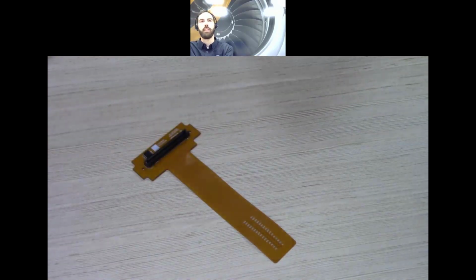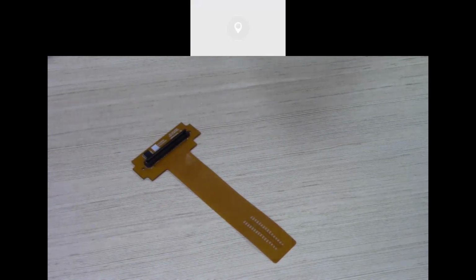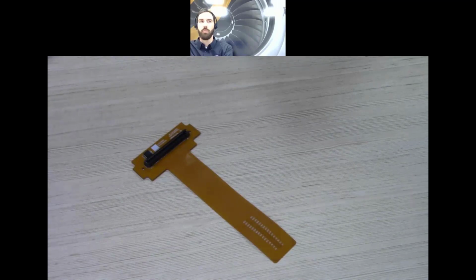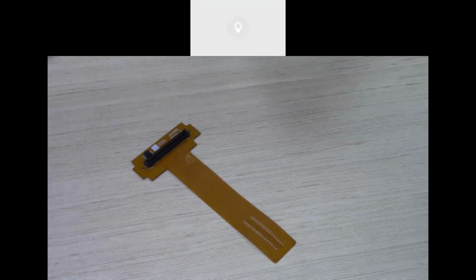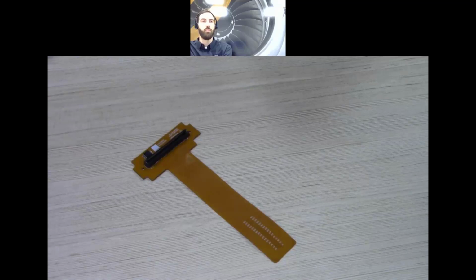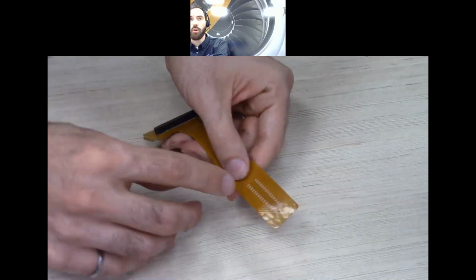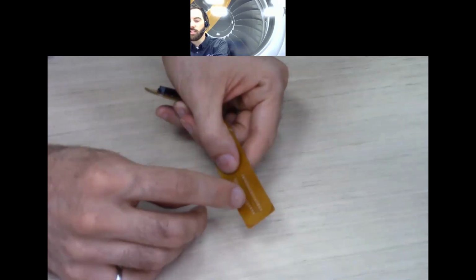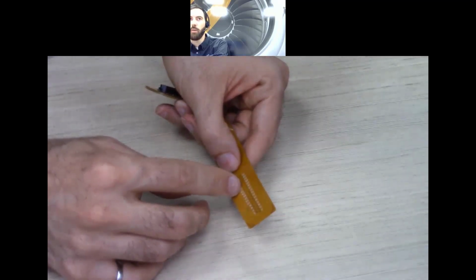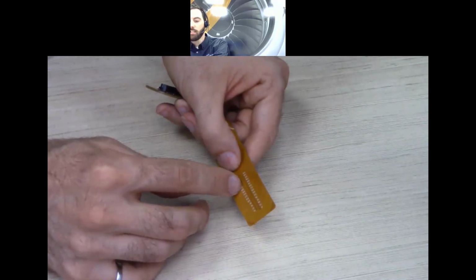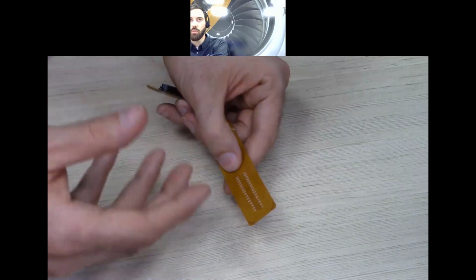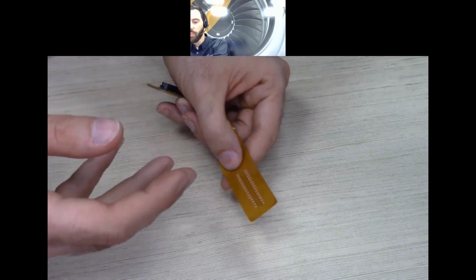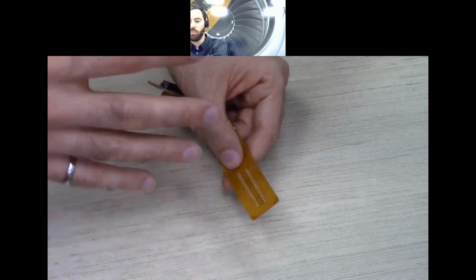But the reason why we're launching this product now and not 10 years ago is that the technology of printing copper into flexible boards has advanced significantly over the last few years, to the point where the coil sensors that you see on the screen here are pretty much as performant as traditional pancake coils that are handmade with copper wire. And the reason behind that is that now they are able to print copper in a very, very dense way, so that the coil sensors that you have here are very dense, made with a very high number of turns. And this translates into more current flowing into those coils, more energy into the magnetic field, and more energy into the eddy currents that will be transmitted into the material.